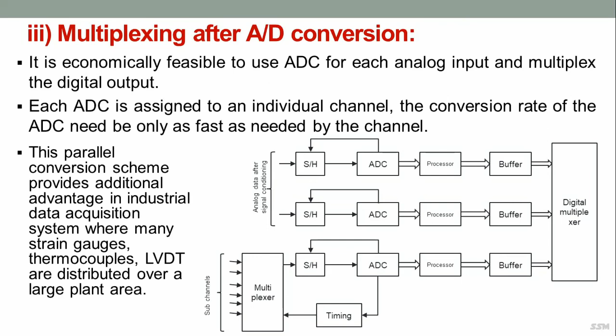The diagram shows a multi-channel data acquisition system using digital multiplexing. The parallel conversion scheme provides an advantage in industrial data acquisition systems where many strain gauges, thermocouples, and LVDTs are distributed over a large plant area. In this multiplexing after conversion system, we can see that each individual sample and hold has its own ADC. Further, it is processed individually and buffered individually, connected to multiple outputs to a single digital multiplexer.